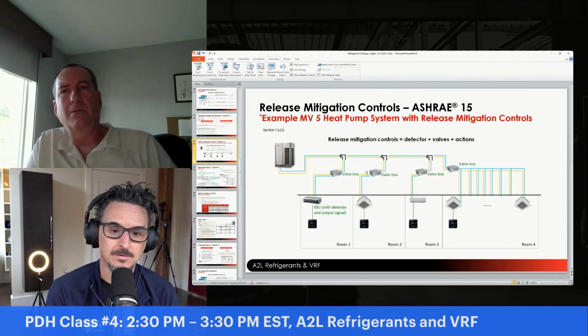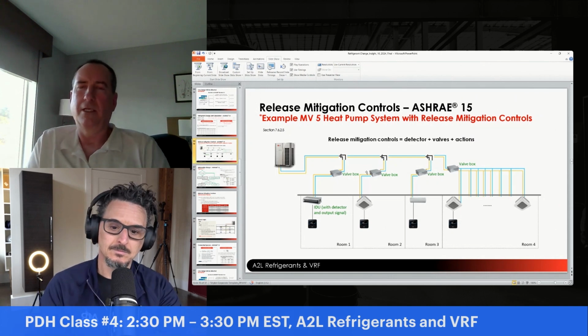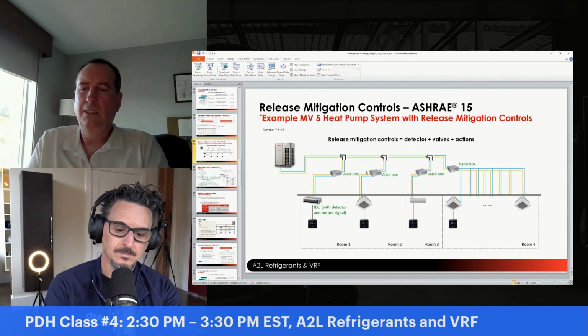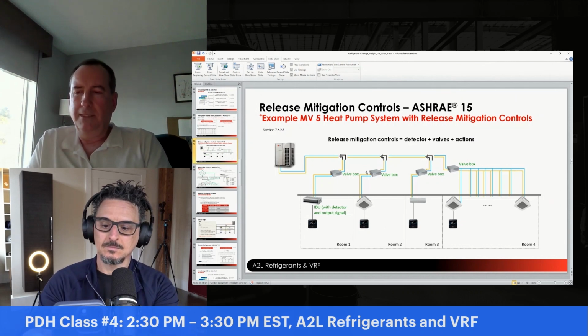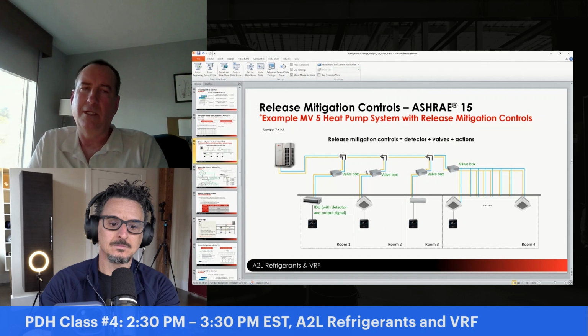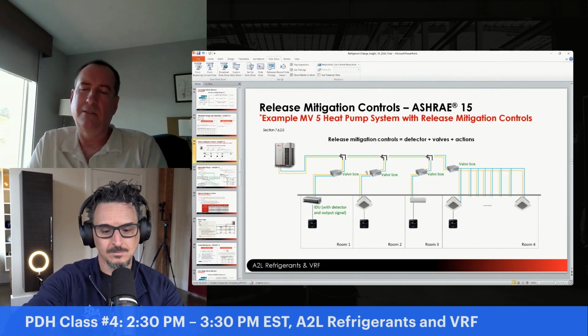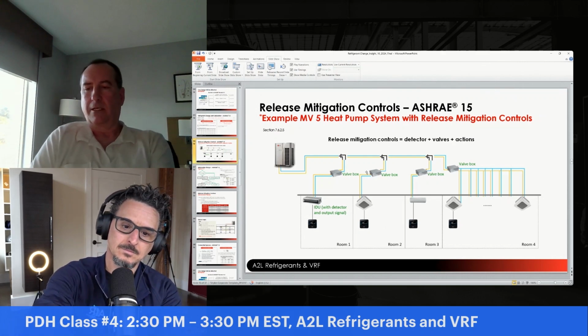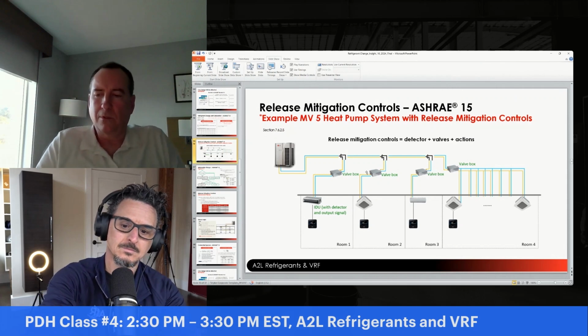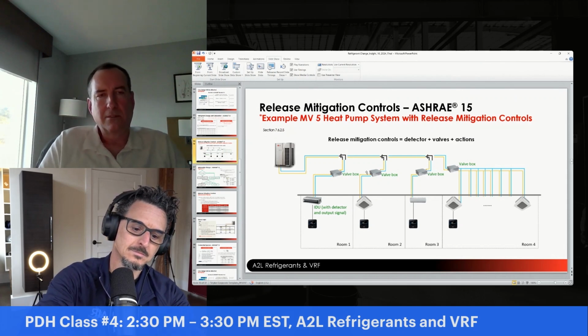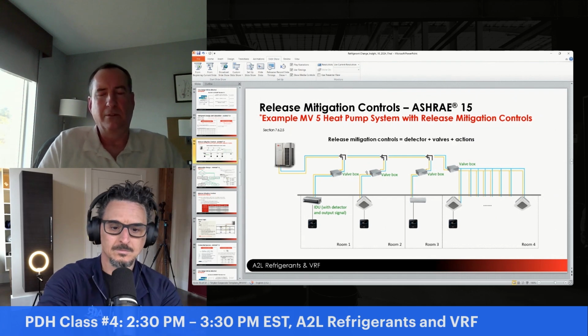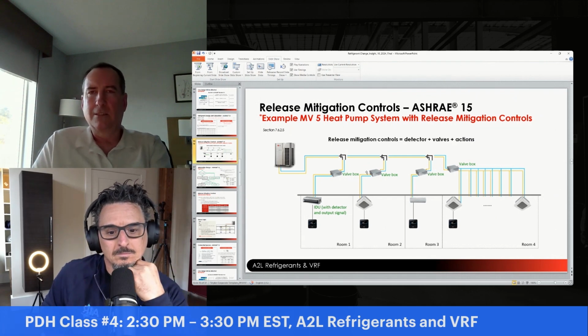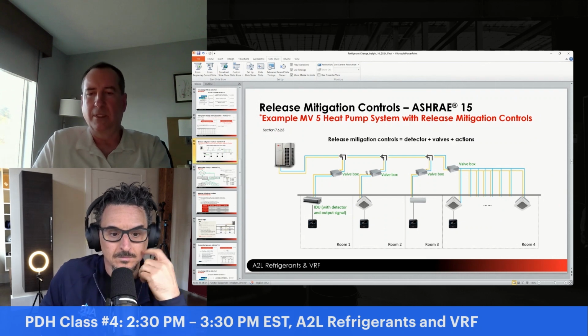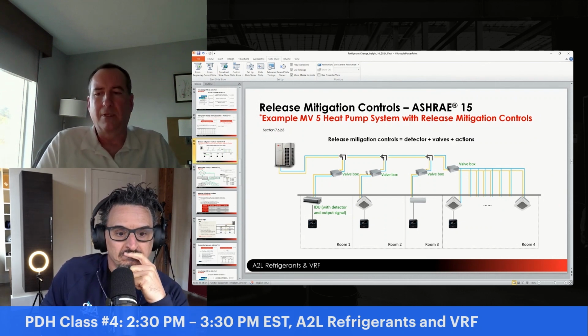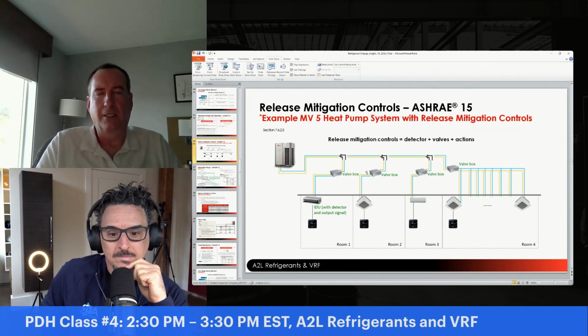So one of the things I mentioned was this concept of release mitigation controls. The minimum room volume and the maximum allowable charge requirements that exist, that's how we had it set up in the old standard. The updated standard gives us much more safety options and tools. So like I said, it gives you a lot more flexibility when you're doing your designs. So just for an example here, release mitigation controls can be used to limit that possible refrigerant charge that could be released into that particular space or zone.